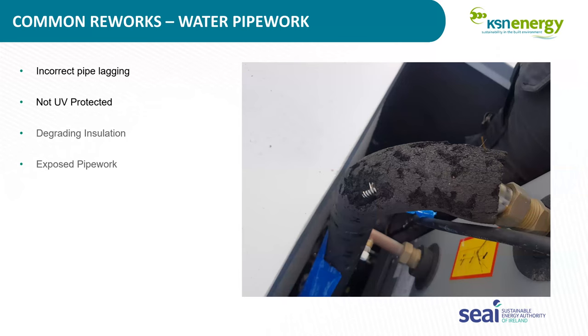I have another image here. And as I said, we're typically about 2 months out after the installation is finished. And if you look at that there, I don't know whether it was birds pecking on it, whether it's just UV from the sun. You can see the bottom of the heat pump, that's a monoblock one. So the bottom of it there, there's no insulation on the pipes.